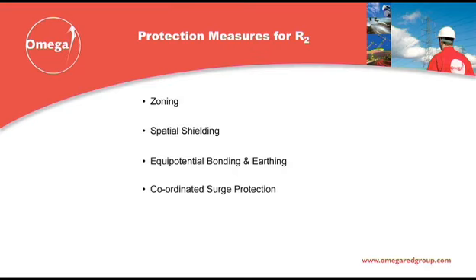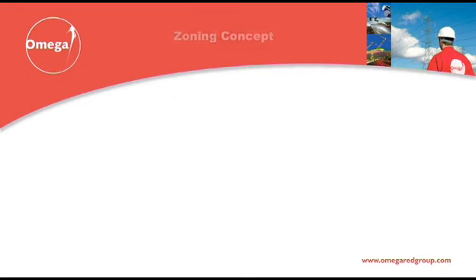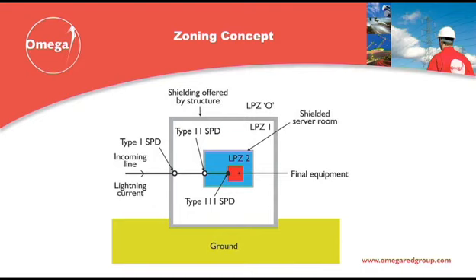The standard approach is protection using four basic concepts, and we will address each of these during this section of the cast. The first consideration is the various lightning protection zones within the structure. These zones are theoretically assigned volumes of space or rooms where the severity of the lightning electromagnetic pulse present in the zone is compatible with the impulse withstand level of the equipment enclosed within each of the zones.